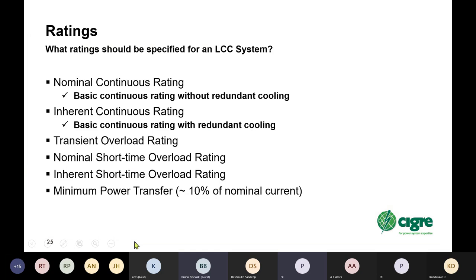Ratings. So what ratings should you specify for an LCC system? You look at the nominal continuous rating, which is the basic rating without redundant cooling. You should specify an inherent continuous rating, and that's a basic continuous rating with the redundant cooling in service. In addition, you should look at requirements for transient overload, which is a shorter time overload, typically in the order of seconds, and short time overload, which is typically in the order of half an hour to several hours. And with the short time overload, there's again the nominal and the inherent, the difference being that the nominal doesn't include the redundant cooling and the inherent includes the redundant cooling.